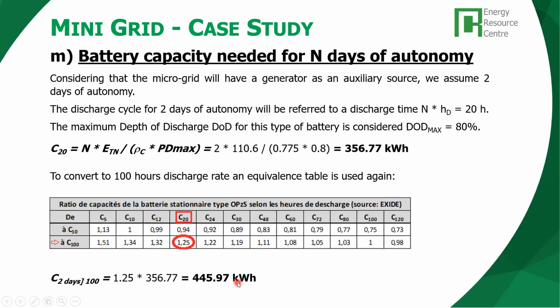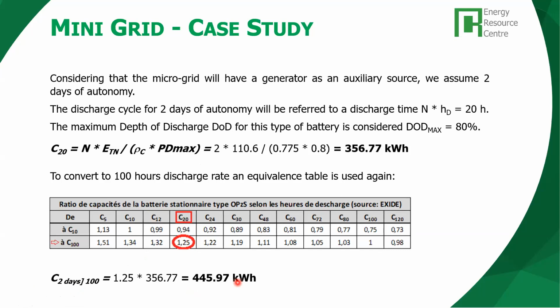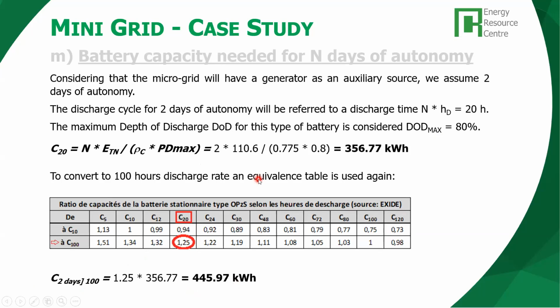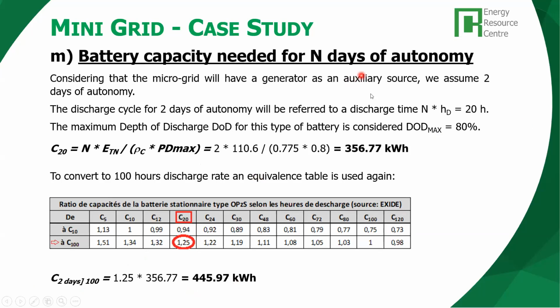But for the battery sizing, remember that is the battery sizing for 1 day. Normally we want to consider different days of autonomy, more than just 1 day, because in 1 day we could have a storm, we could have some clouds. So typically we consider more than 1 day of autonomy. In this example, because we have the genset, we only consider 2 days of autonomy.